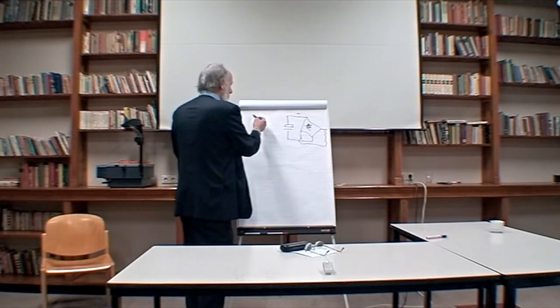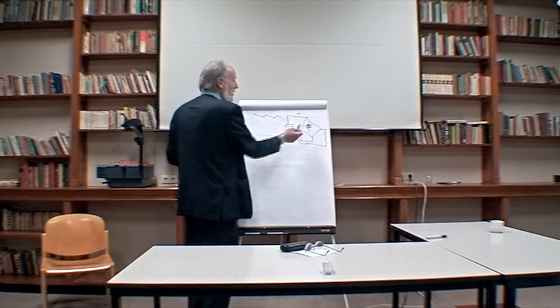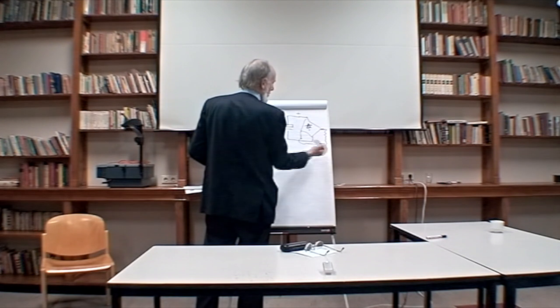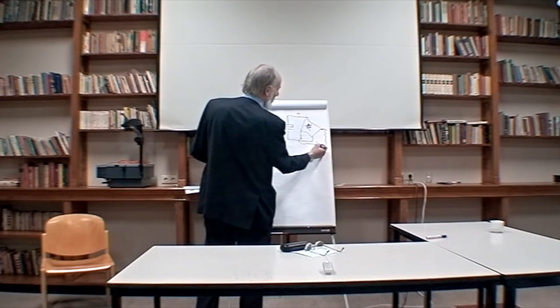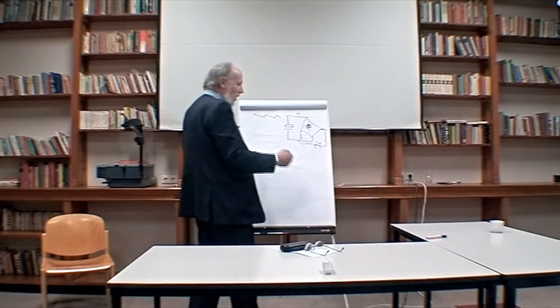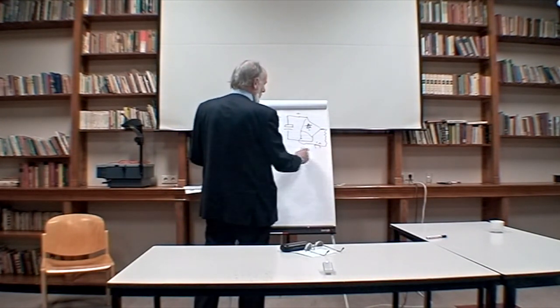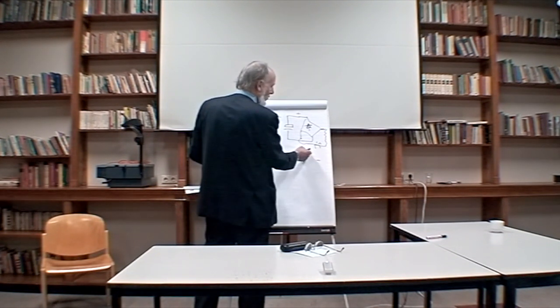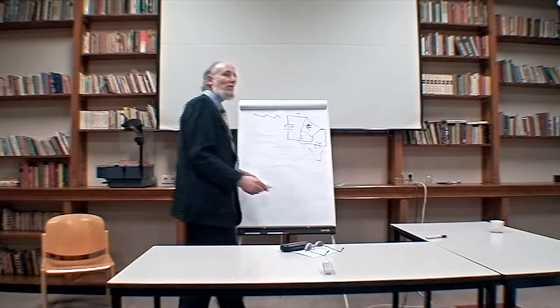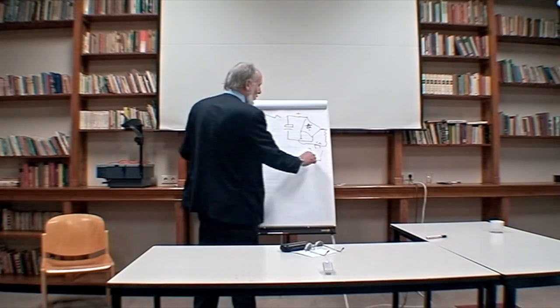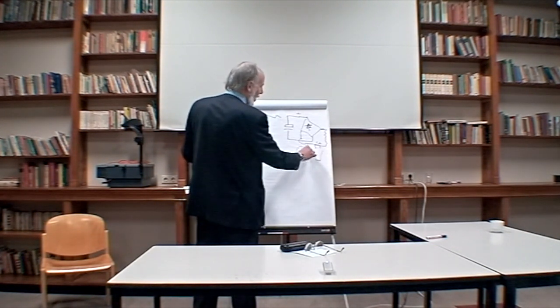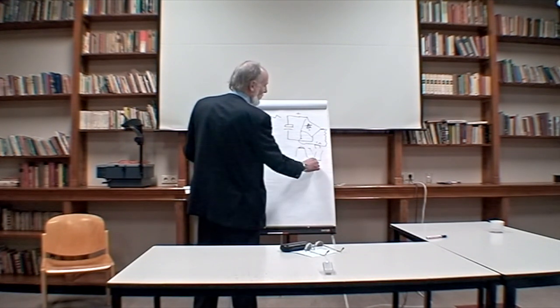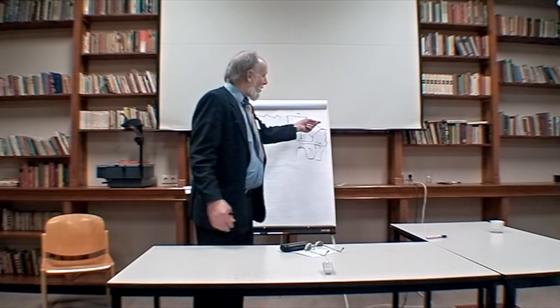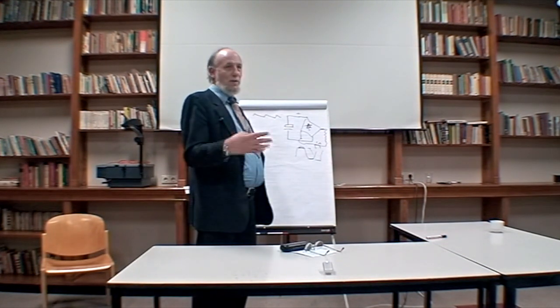And unfortunately, if you look at the ripple, you'll have the instant charge with a slow decay, typical sawtooth. If you analyze the current by putting a current resistor, say 1 ohm here, and taking that off to a scope or a measuring device, you'll see that the current waveform on the sine wave is all at the tops and bottoms of the waveform, and there's nothing much, there's no conduction in the two periods between on the sine wave. So due to the losses in the transformer, the sine wave tends to get the tops and bottoms cut off. This, unfortunately, back to the AC, produces a lot of harmonics.